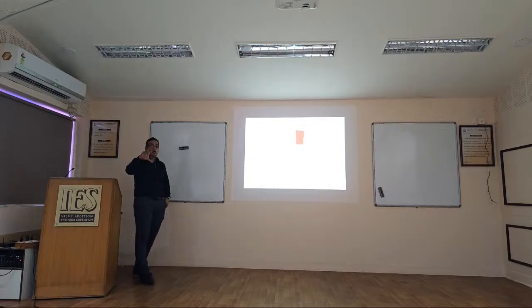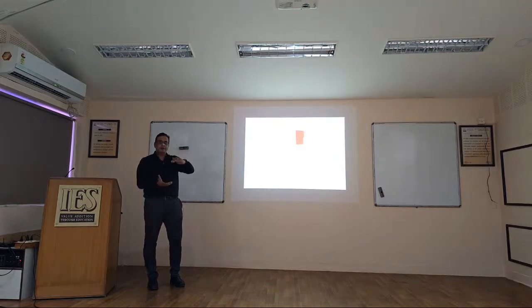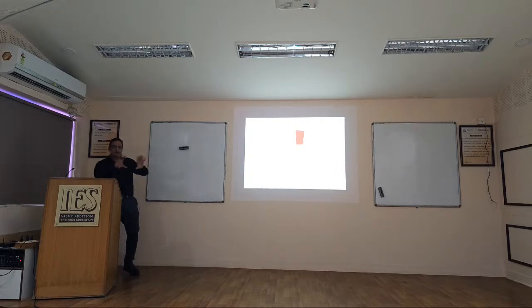The STP again is double height, spanning basement 1 and basement 2, because it needs a minimum height. Generally plant rooms can work within 4.5 to 5 meters, but a sewage treatment plant needs a larger height, about 7 to 8 meters. So that's a consideration you should have — an 8 to 7 meter height for the sewage treatment plant room, whereas otherwise all plant rooms can work within 4.5 to 5 meters in commercial usage.